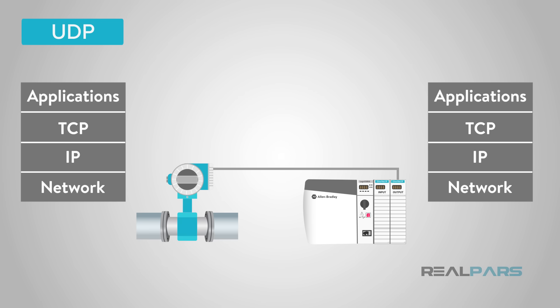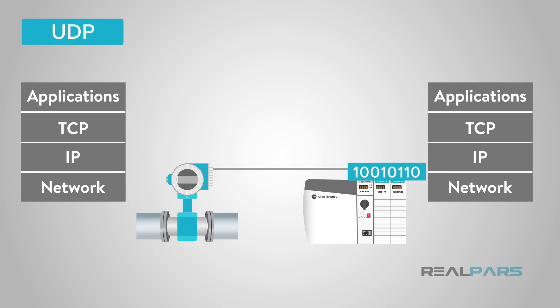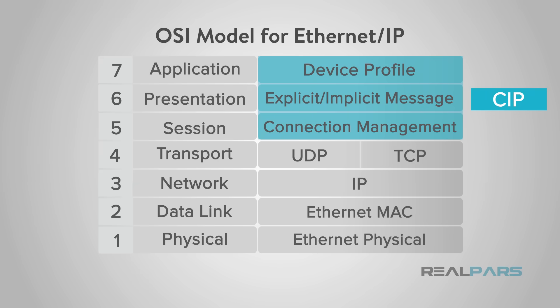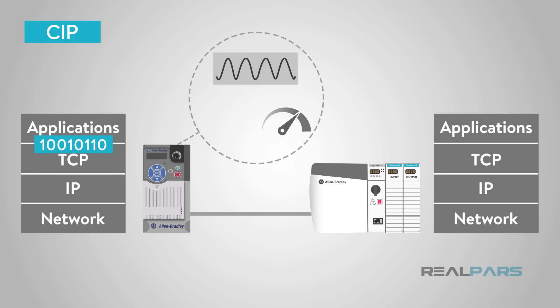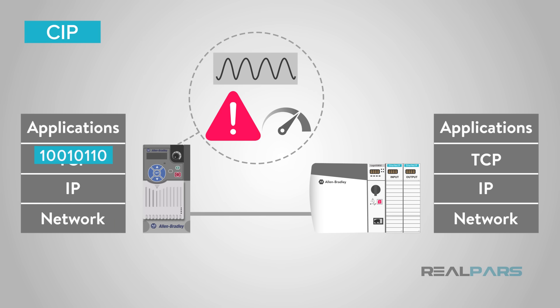This protocol would be used in something like Ethernet I/O on your PLC or a flow transmitter. These devices will constantly send the state of their data. If a packet wasn't received, it's not a deal-breaker, as the next packet is right around the corner. CIP uses object-oriented design to present things like a device profile for a VFD. If you've ever used a CIP message instruction within your PLC device, you know that you research the type of data you desire, such as frequency, speed, or faults, and you add that assembly number to your CIP instruction. The data exchanged is a number of data registers that you in turn map to your tags for desired data.